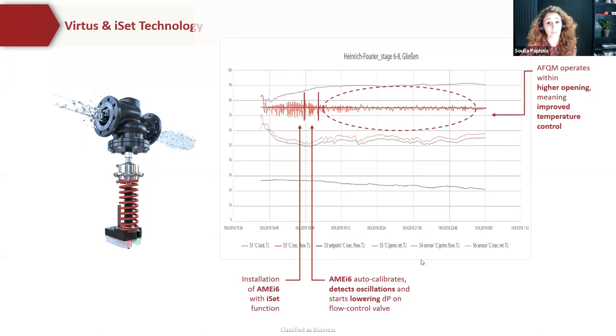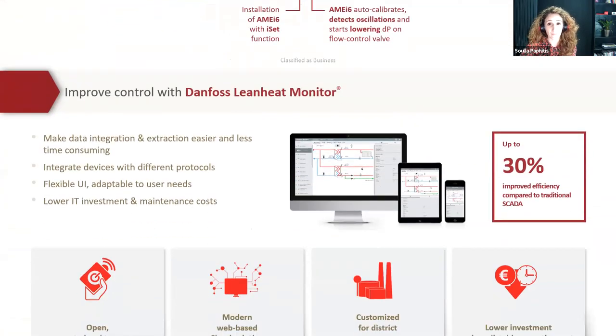So the ISET function monitors flow control signals from the electronic controller, where it detects a signal that is oscillating. This enables it to stabilize the temperature control. It starts intelligently lowering the differential pressure on the flow control valve, and consequently that forces it into a higher opening and out of the non-authority range. If you can move on to the next slide, please.